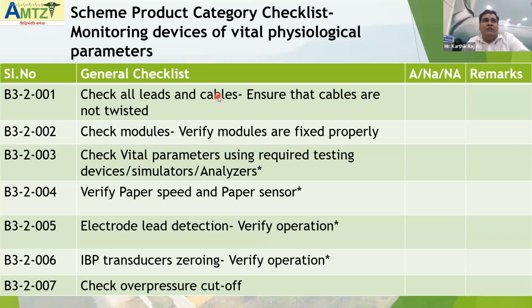For example, the ECG cable you can easily test with a multimeter in continuity mode and check what value is observed. Just checking the continuity alone is not enough. Check what resistance is shown. It should be well within 1 ohm, less than 1 ohm.